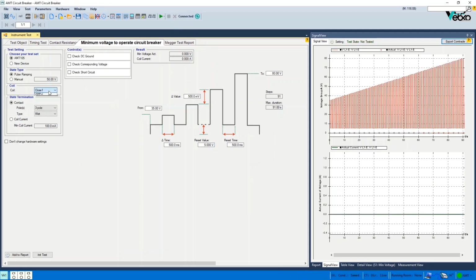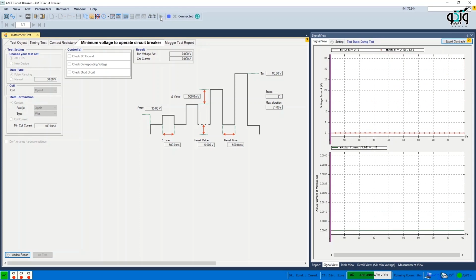To test the open bobbin of the circuit breaker, Coil Open 1 is selected and after pressing Init test, the test is run and the results are added to the Output report.